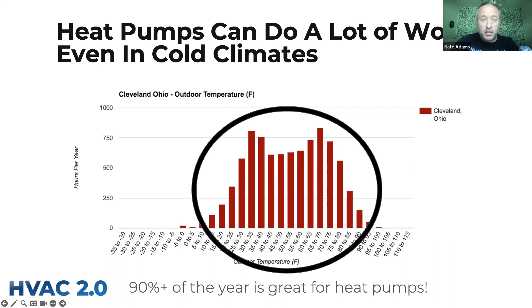A hybrid is a heat pump paired with a furnace, instead of the standard air conditioner paired with a furnace. That means about 90% of the year is actually great for using a heat pump, even if you have some form of furnace as backup. Your backup heat can be whatever—electric resistance, gas furnace, propane furnace, wood. Whatever you choose for backup, the heat pump can handle the vast majority of what most climates need. This gets tricky when you get really, really cold, but even in Canada, most of it isn't that cold.